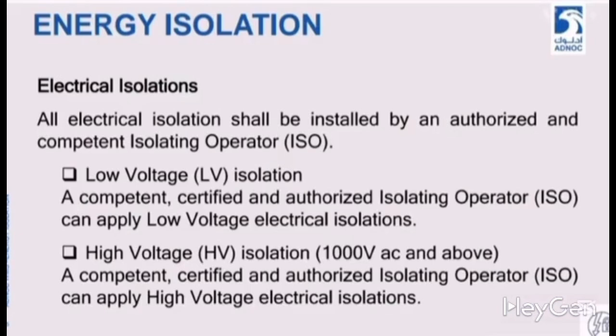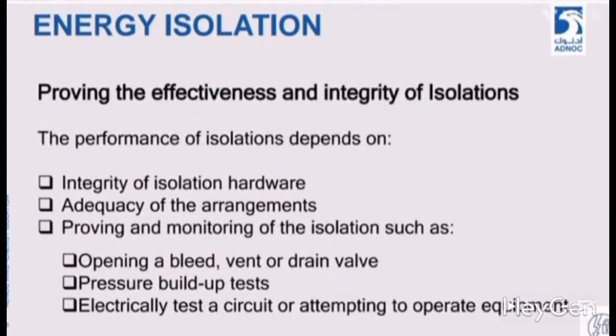The second type comes high voltage, above 1000 volts alternating current. In this too, the same electrical ISO or electrical technician will be authorized to come and isolate the supply of low voltage or high voltage electric equipment. Proving the effectiveness and integrity of isolation.